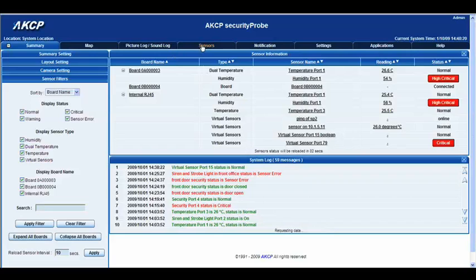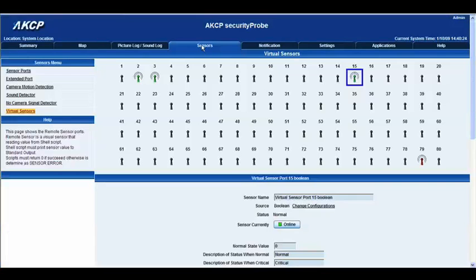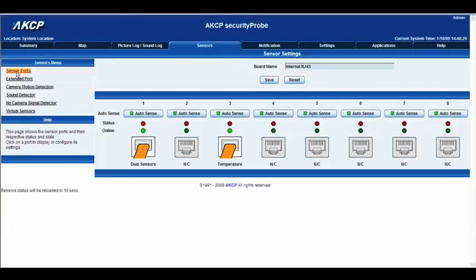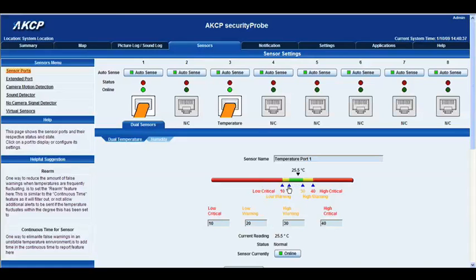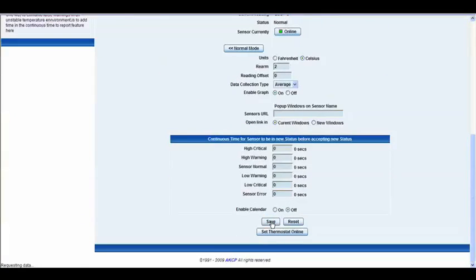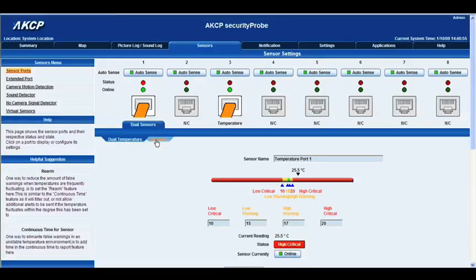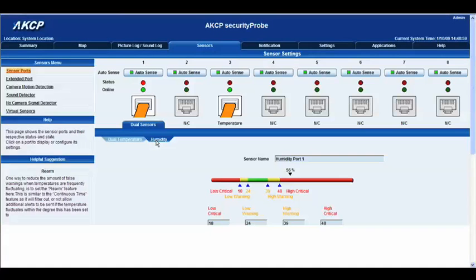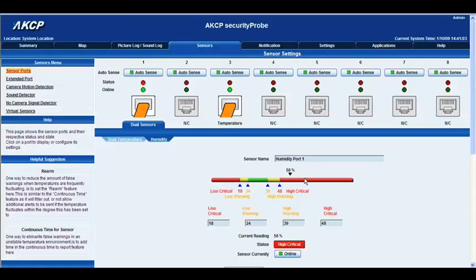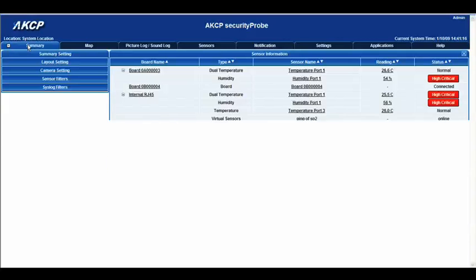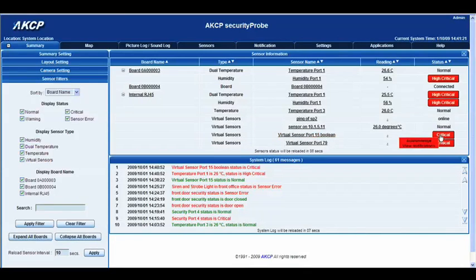Let's get back to our sensors and go to our sensor ports, then navigate to our dual sensors. First, let's take our temperature into a High Critical and save that. Now let's click our humidity tab — and as you can see, our humidity is already in a High Critical. The Boolean virtual sensor isn't going to revert to a High Critical status until both of these are in High Critical, so it would need more than just the one. Now they're both in High Critical. Let's go back to the summary page, and there you can see Virtual Sensor port 15 Boolean is now displaying a Critical status.